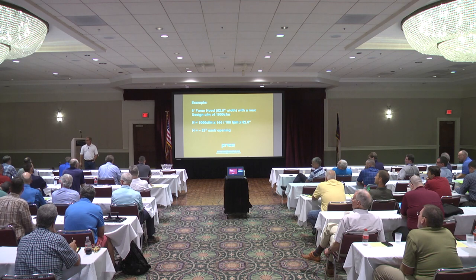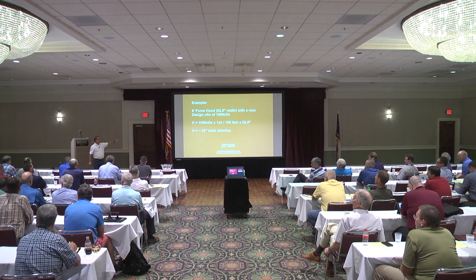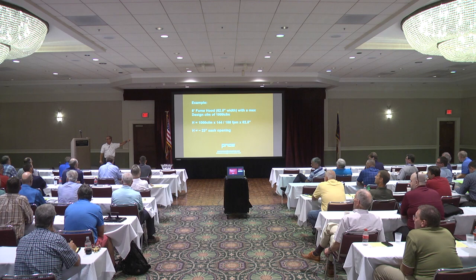Right. And you just made the comment that the TAB professional would say, I don't care, I'm getting design CFM. But you're not. You never got to 1,000 CFM if you raised it to 18 inches. Yeah, I did, I had 125 feet per minute. You're not going to get 125, because I've calibrated my system to do only 100 feet per minute. I'm not going to allow it to go to 125.